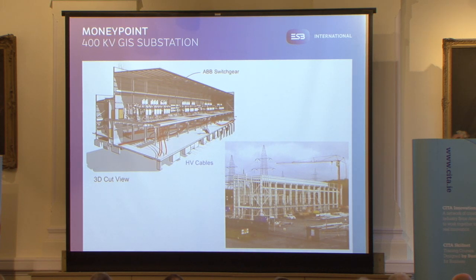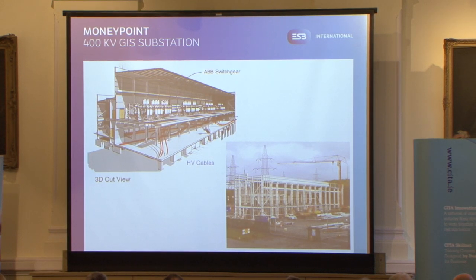The model also gave us good quantities we could pass on to our quantity surveyors — we sorted out the building virtually before construction. We also noted that on earlier substations our requests for information from site were around 140. By the time we got to build MoneyPoint, we had reduced that to just 10 requests for information on that one substantial building. We also point cloud scanned the building and the basement with a laser scanner, and from our model, it was only about three millimetres out overall.